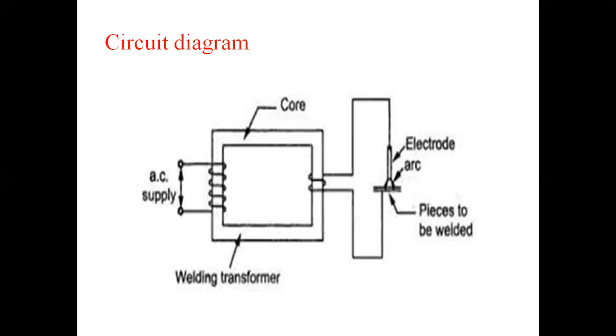Let me tell some applications of transformers. In electrical power engineering, mainly these transformers are used. The transformers make it possible to convert electrical power from a generated voltage of about 11 kilovolts, as determined by the generator design limitations, to higher values of 132 kilovolts or 220 kilovolts or 400 kilovolts, and up to high values like 500 to 765 kilovolts, thus permitting the transmission of huge amounts of power over long distances to appropriate distribution points, a tremendous saving in the cost of transmission line as well as in the power loss.